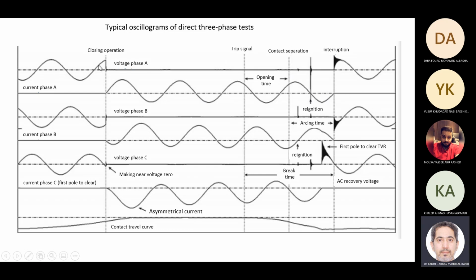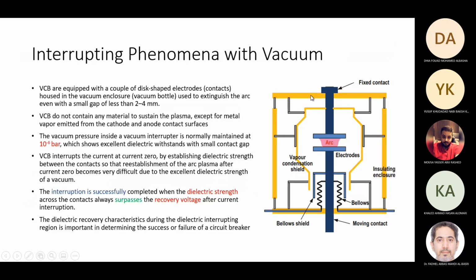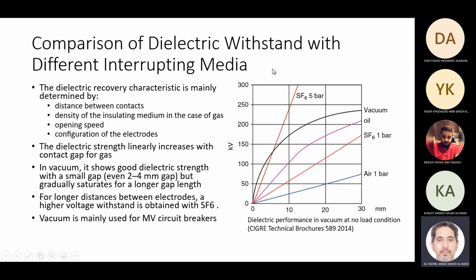This is the voltage across contacts. When it's closed, the voltage across the contacts is 0, right? The current is flowing through the contacts. Sometimes the breaker takes a longer time to break the currents because of this reignition of the arcing. I'll come to this later. When I say dielectric strength of the medium, I mean the insulation used. Is it air or SF6, oil or vacuum? All of them have different dielectric performance.